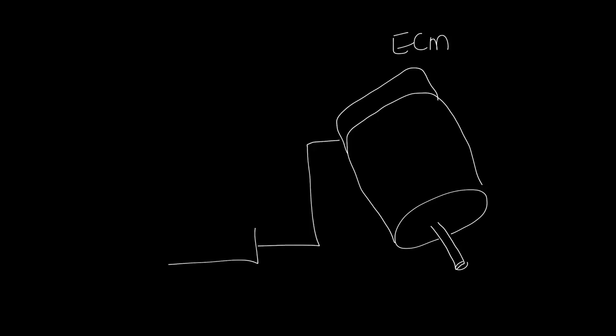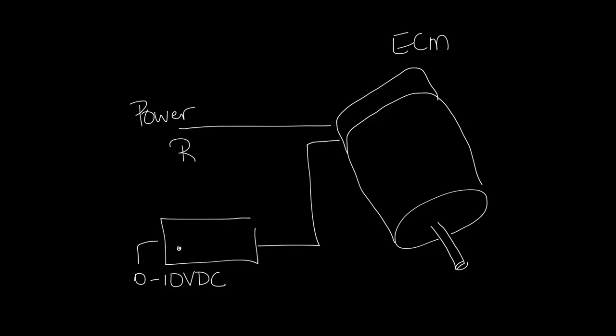The remote PWM speed control is designed to accept a 0 to 10 volt DC signal from a VAV controller or thermostat in order to set the motor speed. This feature can be used several different ways. It can allow the unit to be balanced or rebalanced without physical access to the unit. It can also be used to change the motor speed for various operating modes.